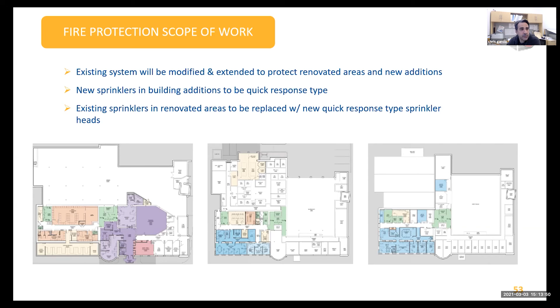And then in the renovated areas, just these colored sections of the plans, we would expect that we'd replace the existing sprinkler heads with new. Depending on what we do with the ceilings, we'll work that with Janet and her team. If ceiling heights change, then maybe some of the piping would need to be replaced. But if everything stays the same, there are no coordination issues with new ductwork or anything like that, we would expect the existing piping to remain, and we would just provide new sprinkler heads in new ceiling areas to deal with the architectural layouts. So in terms of fire protection, that would be the scope of work.